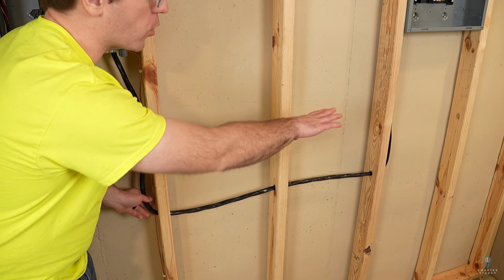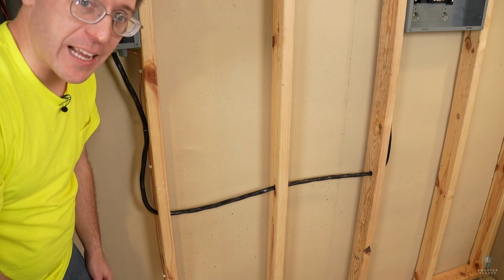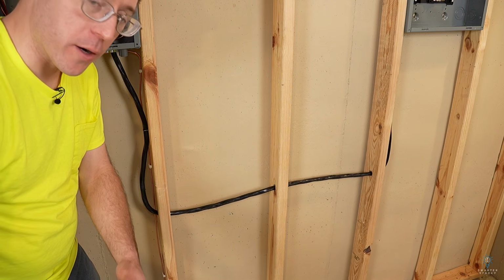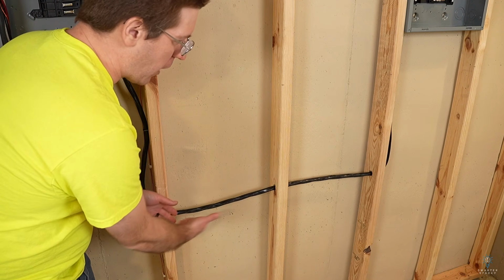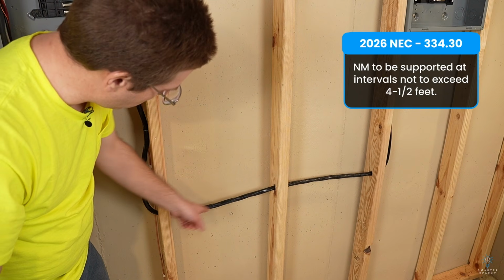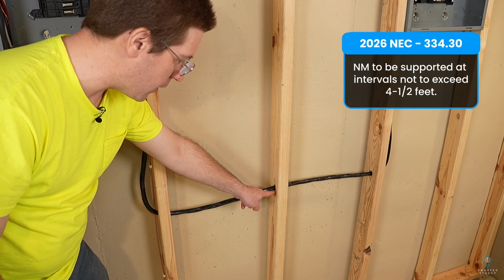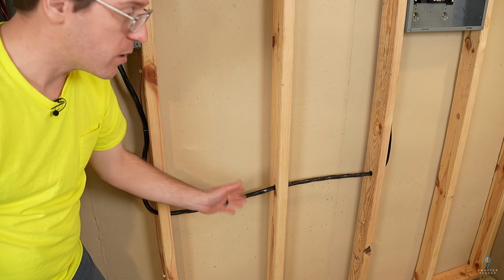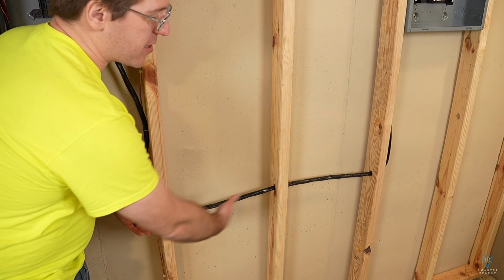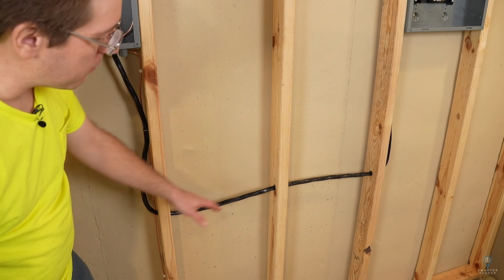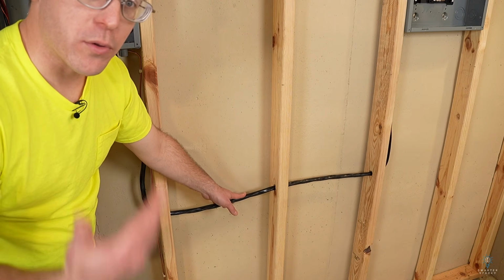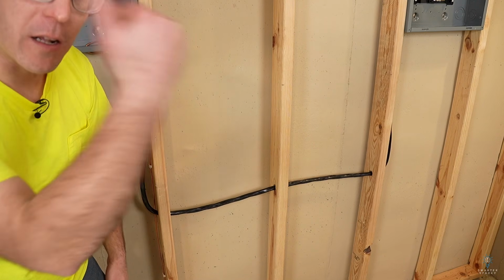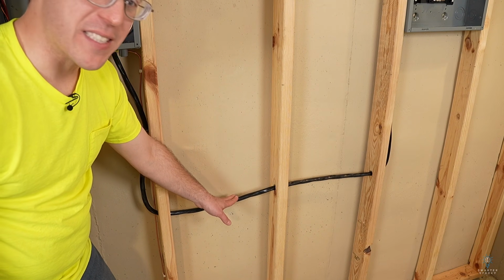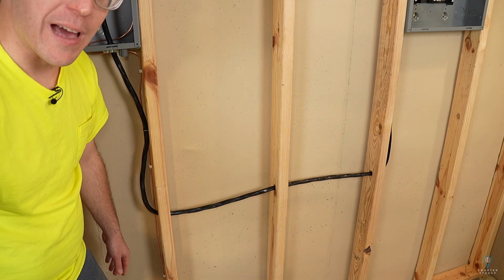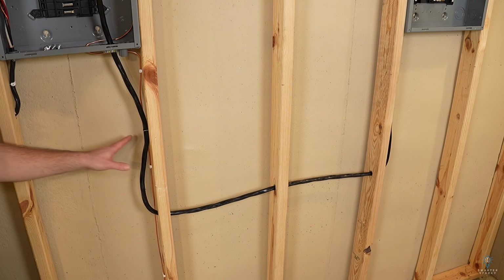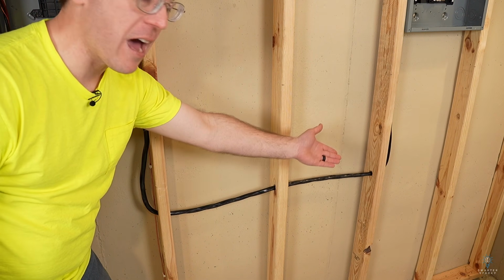If this were a longer run, maybe up inside of an attic going to a sub panel in another part of the building, we would have to support this wire every 4.5 feet. Now, because we're going through studs, it's actually inherently supported every 16 inches as it goes through each stud. So we don't actually have to staple anything as it goes horizontally, but if these were up in rafters or going through floor joists or whatever, parallel to floor joists, we would actually have to staple this every 4.5 feet along that route. So it's within 12 inches of the panel and then every 4.5 feet thereafter.